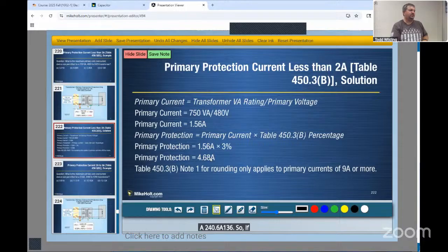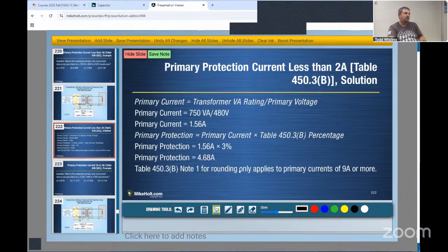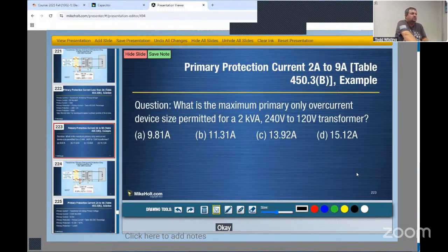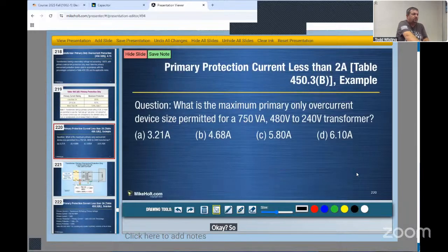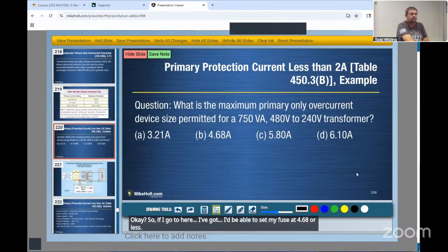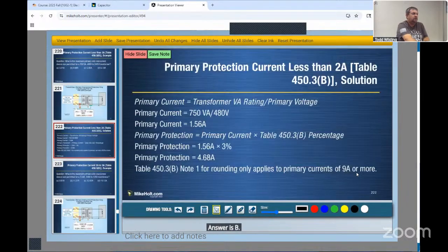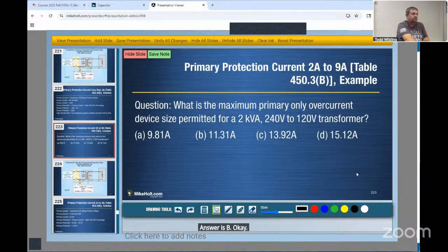So if I've got 4.68, what size fuse do I have to have? 3. Can't go up because I'm not at 9 amps. Note 1 applies only to 9 amps or more. Okay. So if I go to here, I'd be able to set my fuse at 4.68 or less. Answer is B. Okay. So any questions there? It's kind of confusing. It's kind of tricky.